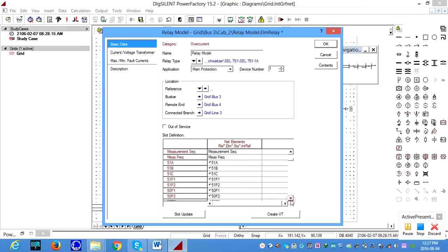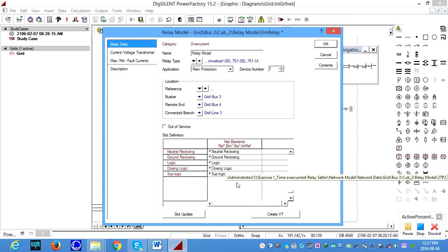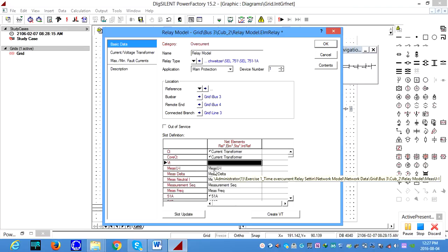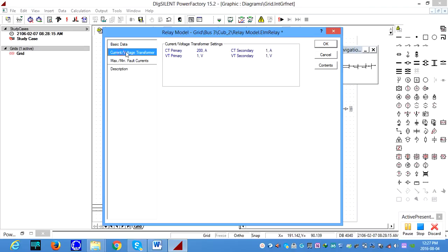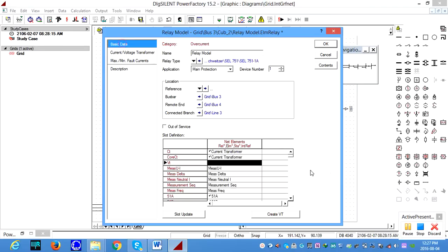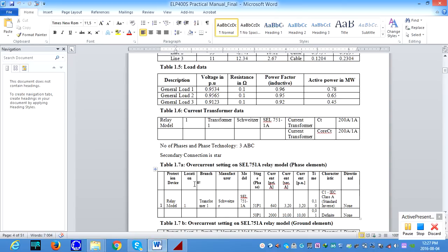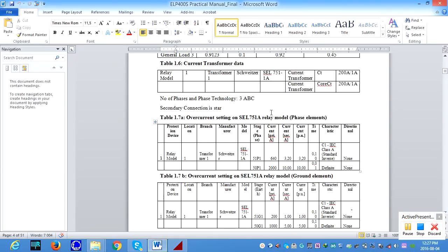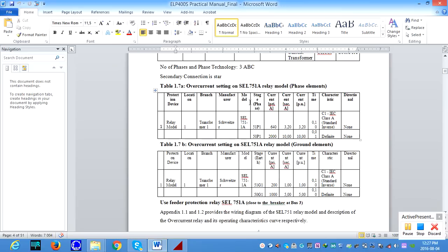And we also make sure the elements that must be set here. We go to the lab manual and come back for the settings of this one. Okay. The current transformer, you can see 200:1 amps. We don't worry about the VTs for this experiment. Okay. We go back to the manual. Okay, current transformer we did, and for the overcurrent relay settings, there are two things that are important. First, we need to define the phase elements, and then we also want to define the ground elements.